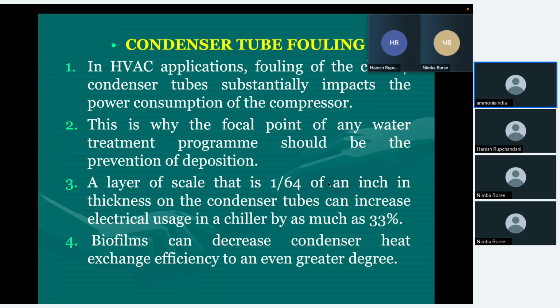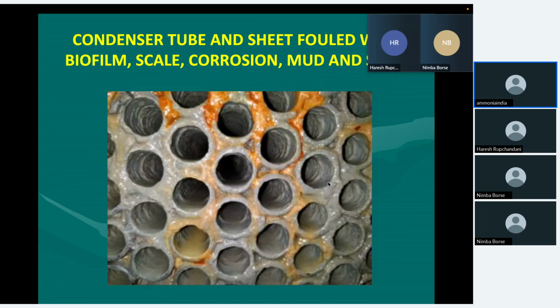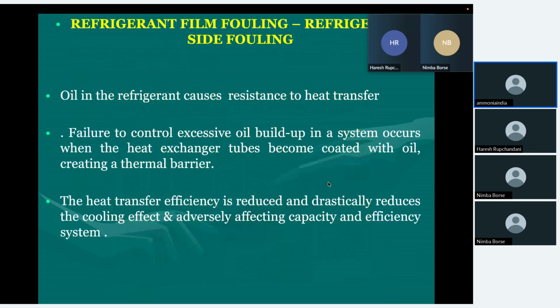The biofilms can also decrease condenser heat exchange. So this is the fouling of condenser tubes, fouling by corrosion, mud, etc. Everything accumulates in the tubes. Then there is refrigerant film fouling. The oil in the refrigerant causes resistance to heat transfer, and some oil is carried in the system. Fouling by oil occurs when the heat exchange tube becomes coated with oil. So removal of oil using very high efficiency oil separators, so that minimum oil is carried in the system, is very, very important.